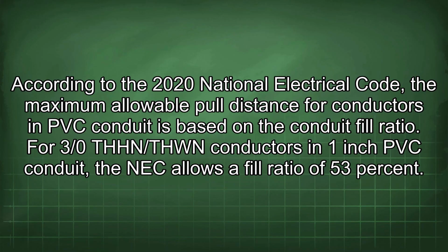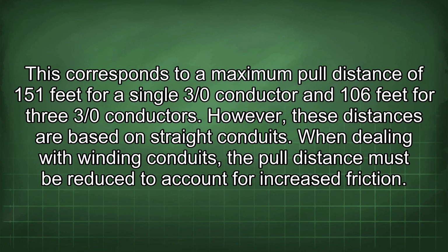According to the 2020 National Electrical Code, the maximum allowable pull distance for conductors in PVC conduit is based on the conduit fill ratio. For 3/0 THHN/THWN conductors and 1-inch PVC conduit, the NEC allows a fill ratio of 53%. This corresponds to a maximum pull distance of 151 feet for a single 3/0 conductor and 106 feet for three 3/0 conductors. However, these distances are based on straight conduits.